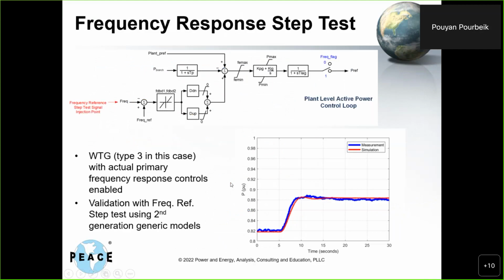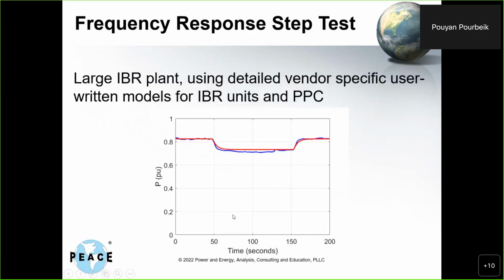Now, frequency response - again, same thing. We can either use a standard library model, here's an example injecting a frequency reference step test, measured versus simulated. And here's an example of a large IBR plant with very detailed vendor-specific user-written models for the individual IBR units and the PPC, again doing a frequency step test. Again, you get a good fit.